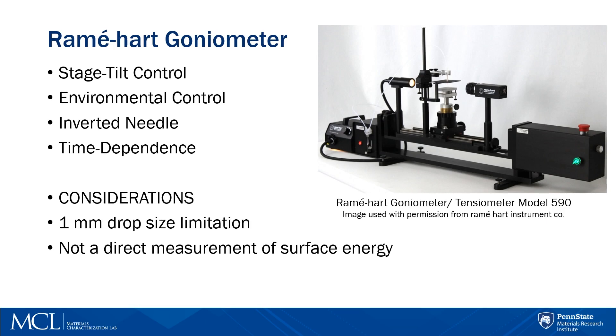As for considerations and limitations, the largest limitation is that the smallest drop size we can achieve is right around one millimeter — we can't go much smaller than that. The other thing to consider is that we're not directly measuring the surface energy. Surface roughness, chemistry, the heterogeneity of the surface, and the choice of liquid will all have an effect on the contact angle. So it's important to choose a model that best fits your material system.